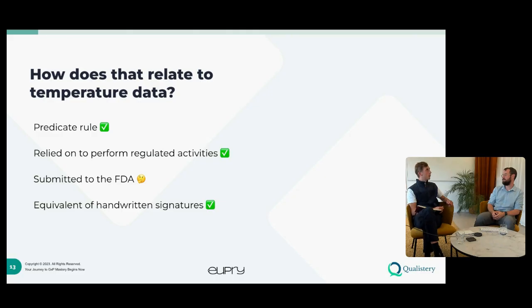Right. So if you have, let's say, a USB data logger, and once a week you need to empty it to a computer and you need to log it, it is an action, right? And then you would need to document your signature somewhere. Yeah, exactly, in a compliant manner. So that's a very good example: extraction of data from a data logger.